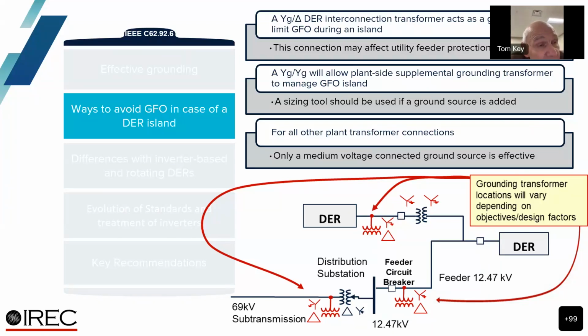But the other thing you do to keep the voltage down is you pick a transformer connection, and you can see in the first top line there, when you have a delta on the DER side, then it actually does provide effective grounding. In fact, sometimes if it's solidly grounded, it provides too much of a path for fault current, and so it requires some additional coordination when you add that kind of a transformer.